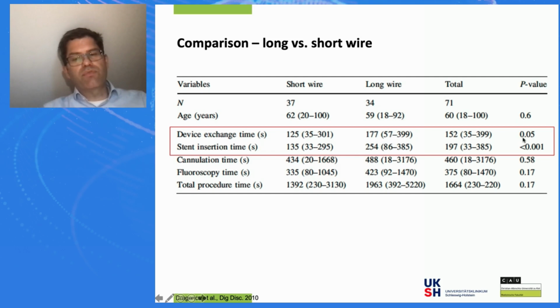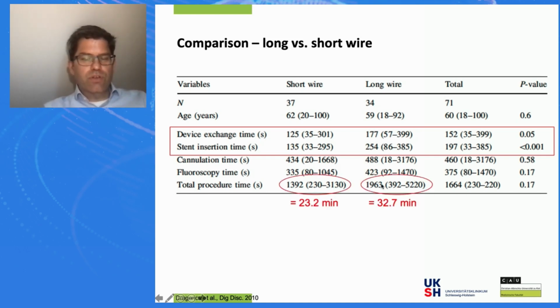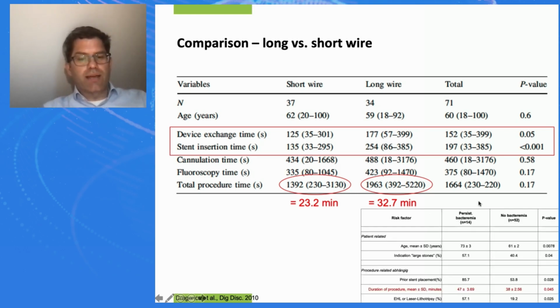Total device exchange time almost failed to reach statistical significance. When you have a closer look at the total procedure time, it is almost 1,400 seconds compared to almost 2,000 seconds. I have no idea what seconds means in minutes. That's why I calculated this for you. It's 23 minutes compared to 32 minutes. And again, we have a delta, short wire versus long wire, in favor of the quicker procedure time, 9 minutes quicker with the short wire system. And keep in mind, exactly these 9 minutes came up during this Tosani study with a risk of bacteremia. So probably, though a direct comparison does not exist, we have a quicker procedure and potentially have a safer procedure with the short wire ERCP.